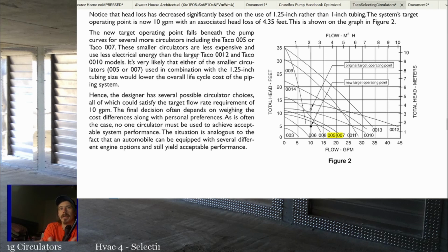The bigger you can make the duct, the better, up to a certain point. Again, we want to have a minimum velocity in both cases a lot of the time, but it's usually pretty hard to hit that number. So then you can use a smaller circulator, and in combination with the 1.25 inch pipe size, you'll lower the overall life cycle cost of the piping system. And that's the other thing to think about when you're designing something, the initial cost. So 1.25 inch pipe costs more upfront than the 1 inch pipe.